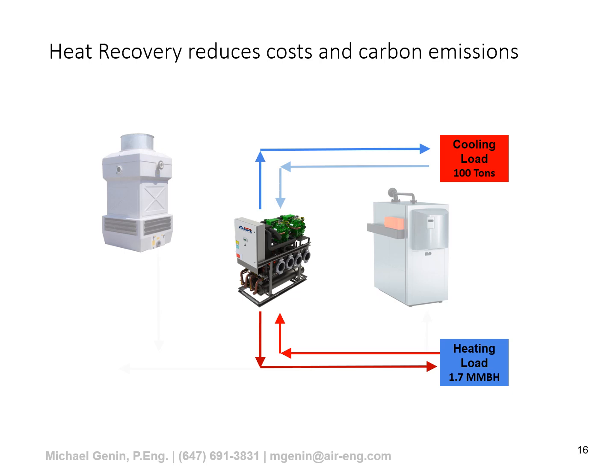So what if we used the waste heat from the chiller to serve this heating load of 1.7 million BTUs? Well, in this example, we're able to shut off the cooling tower for this simultaneous load, and we're able to shut off the boiler or greatly reduce its use by 1.7 million BTUs. And we're going to use perhaps a more specialized heat recovery chiller to do this load. That heat recovery chiller will consume a little bit more electricity. We've gone from 75 kilowatts to 144 kilowatts. We've shut off the pump to the cooling tower. We've shut off the cooling tower itself, and we've shut off the boiler.